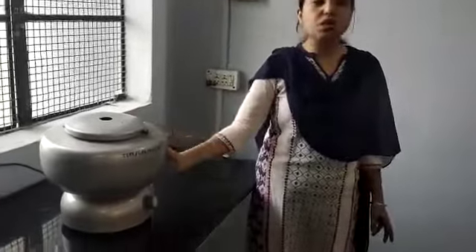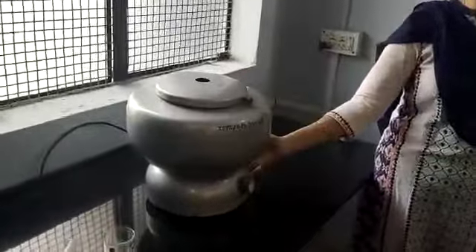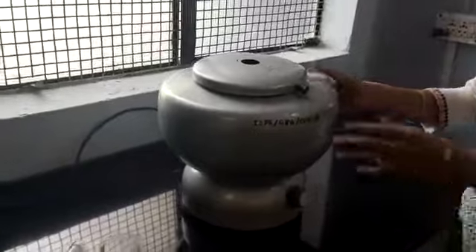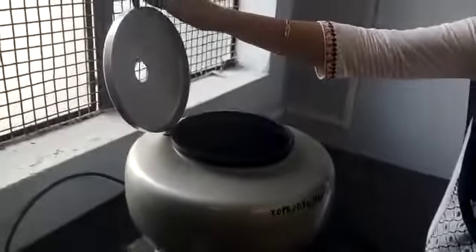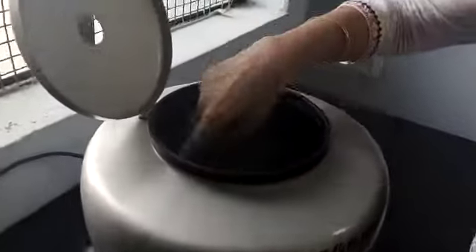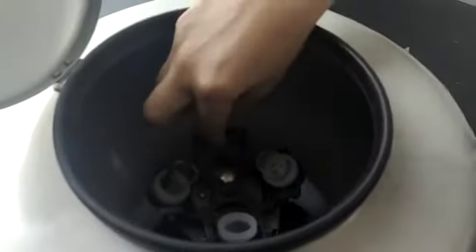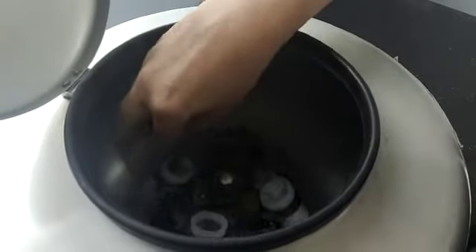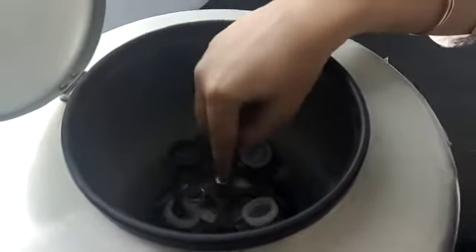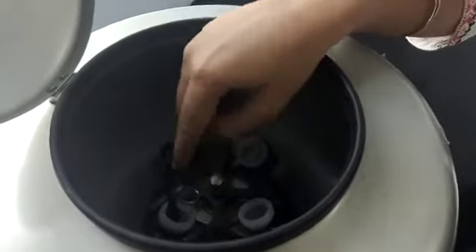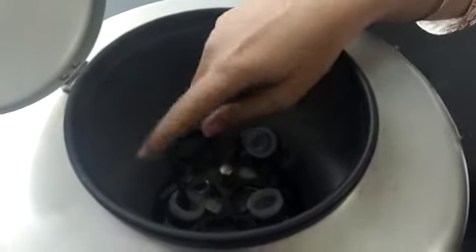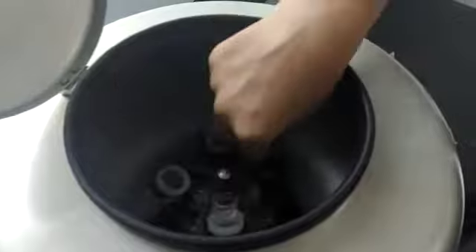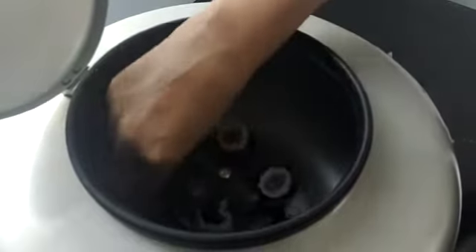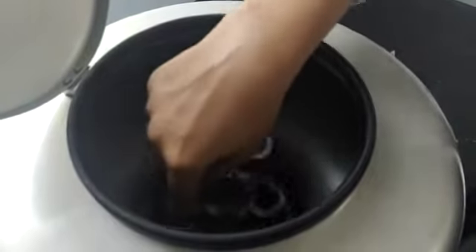Let us first become familiar with the construction of the centrifuge, or the different parts present in this equipment. This as a whole is known as a centrifuge. This is called the centrifuge lid. Inside of this is the centrifuge chamber. This is the rotor. This bucket is called a rotating bucket. This rotor is connected to the shaft. This shaft is connected to the motor, which when switched on will rotate this bucket in revolutions, counted as RPM, revolutions per minute.